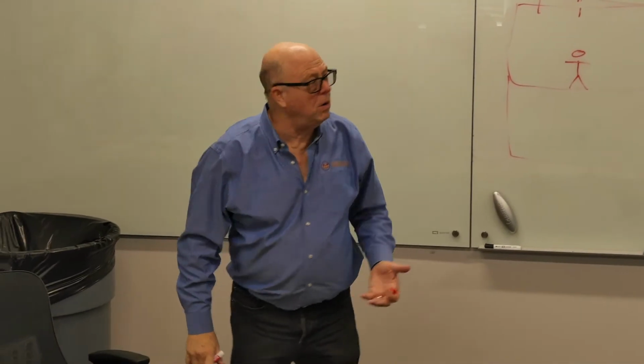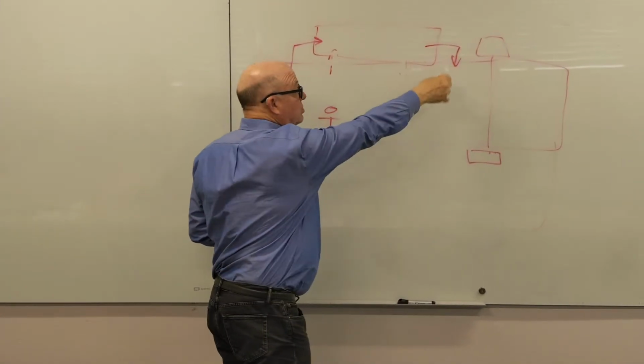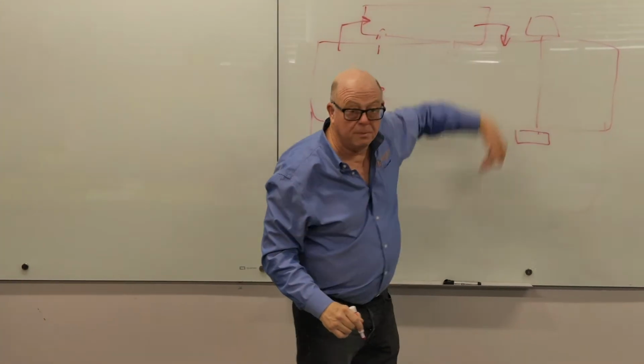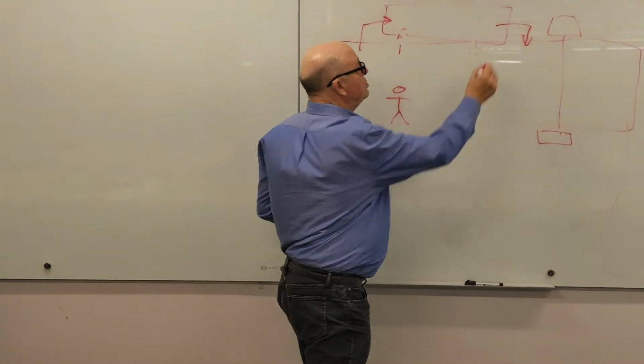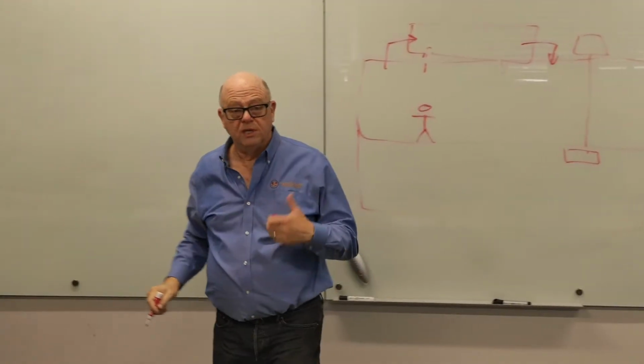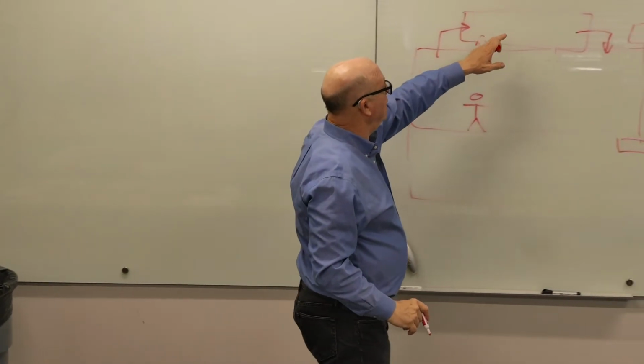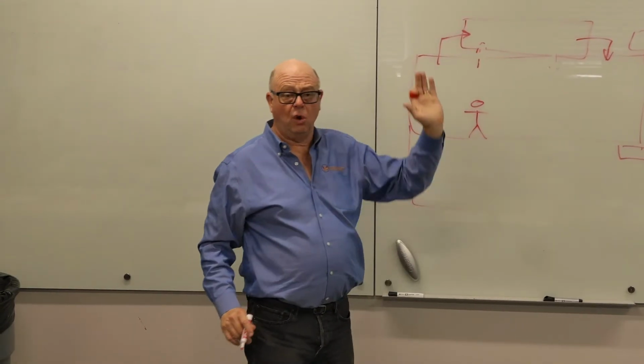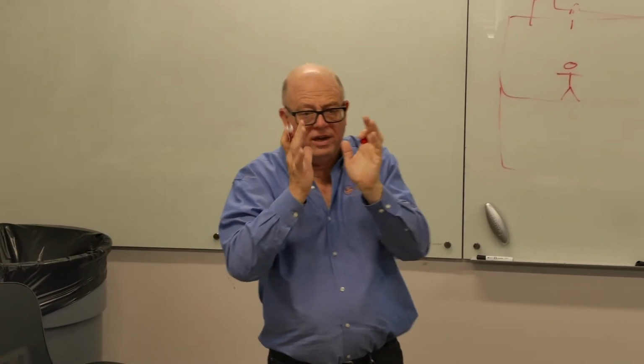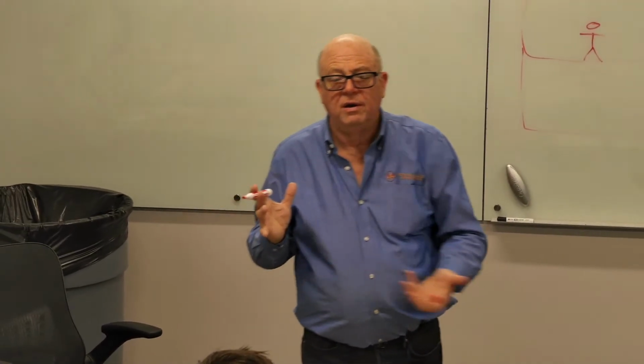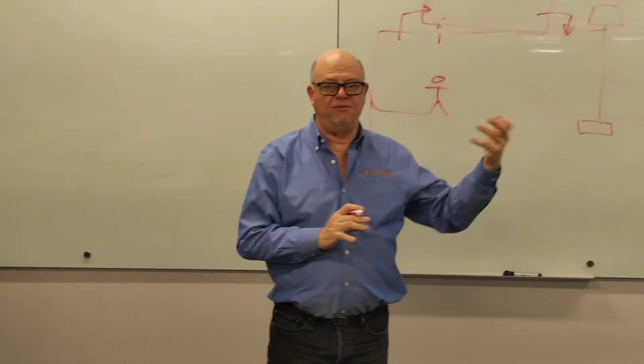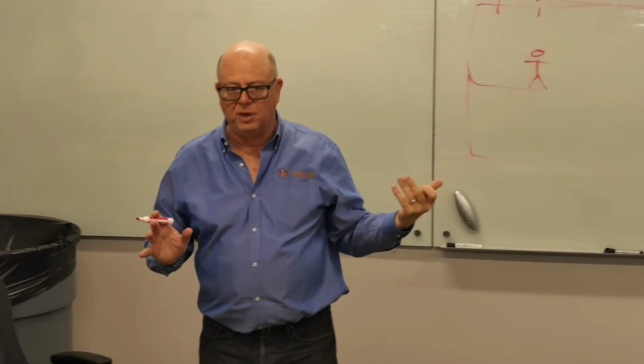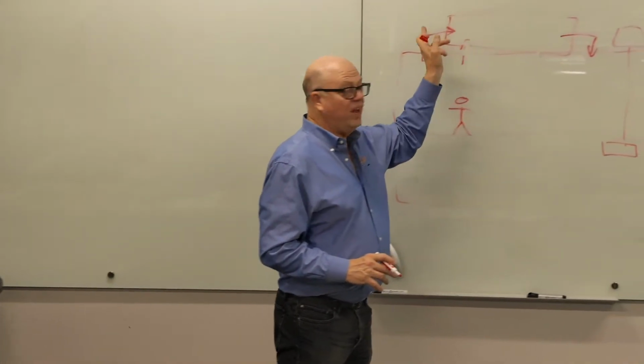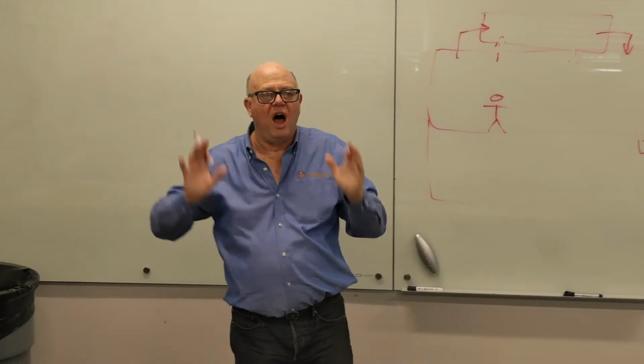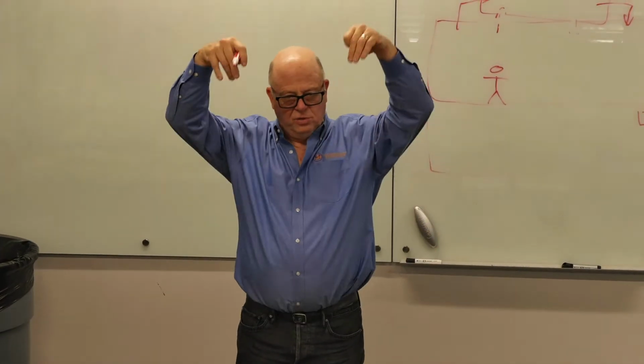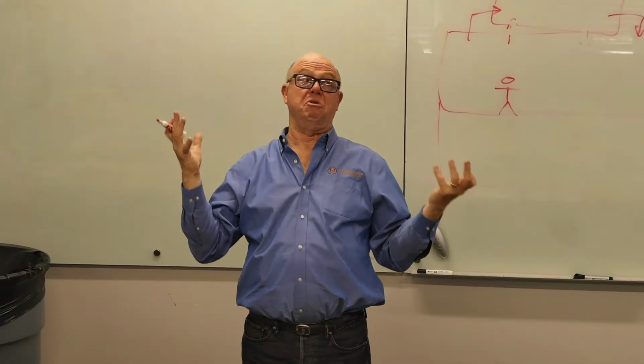Because acoustically now, you've got, and it's a little more static pressure because we've got to come out, got to make a bend, got to go down. But this is lined duct, and it will attenuate the sound depending on the piece of equipment you got. That return air duct opening is probably just the other side of a filter and a cooling coil from the fan. It's probably not far. It's the other side of a little piece of sheet metal from the compressor, and the condenser fan. So it's not the optimum quiet thing to use a downshot if there's going to be somebody right under it who's going to be picky.